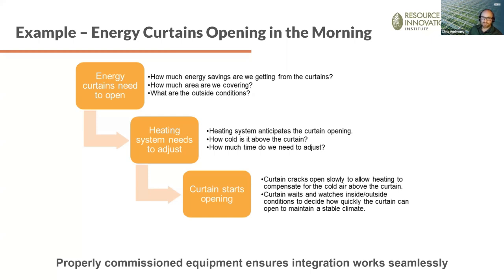We're going to ask how much energy savings we are getting from the curtains. Typically, that is a spec that's provided by the curtain suppliers. Then we need to know how much area we are covering for that specific control area, and what the outside conditions are. Once we have all that information put in on initial commissioning, we get into that situation where the curtains want to open in the morning. So our control says, okay, we want to open the curtains. First thing that needs to happen is the heating system needs to adjust. So the heating system anticipates the curtain opening.